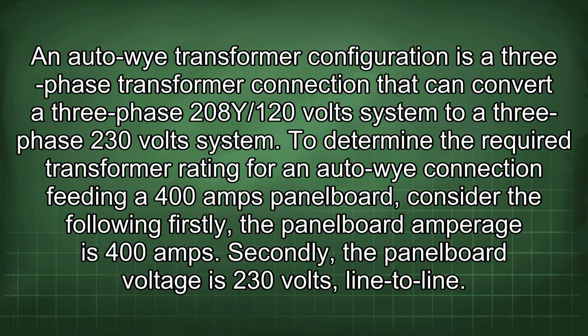An Auto-Wye transformer configuration is a three-phase transformer connection that can convert a three-phase 208Y/120V system to a three-phase 230V system. To determine the required transformer rating for an Auto-Wye connection feeding a 400 amps panel board, consider the following.